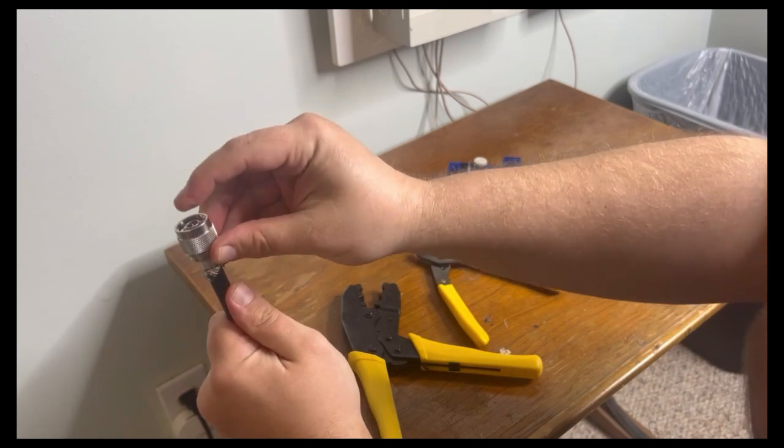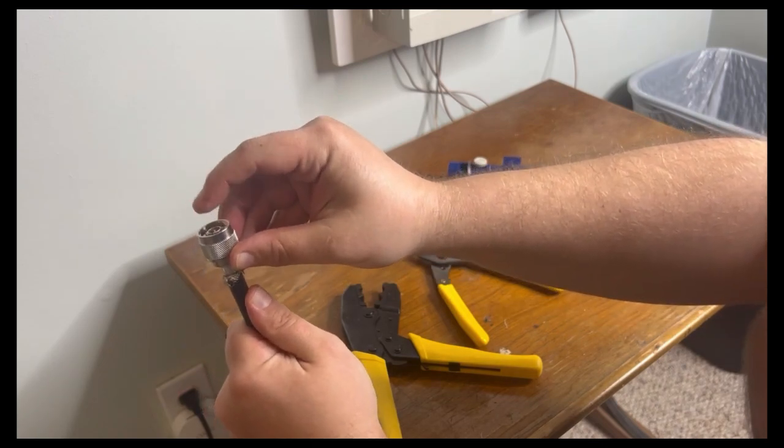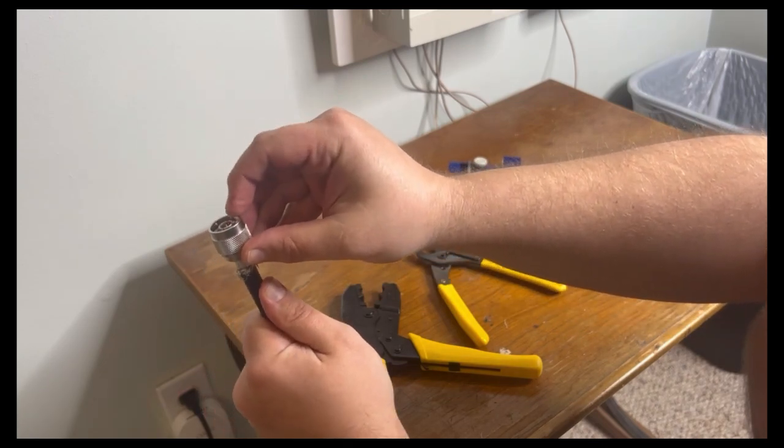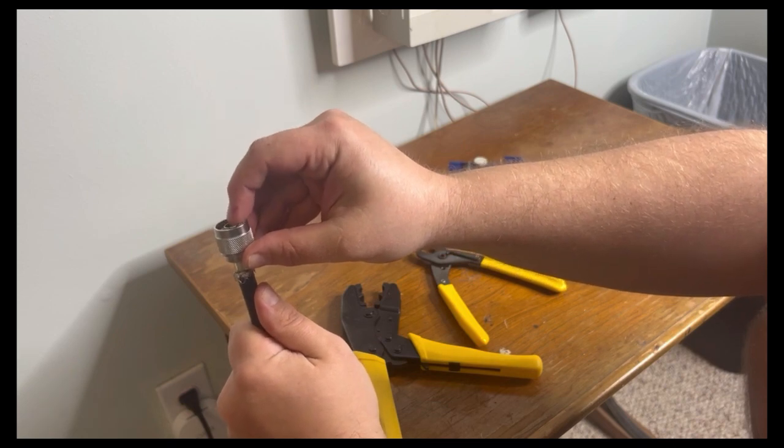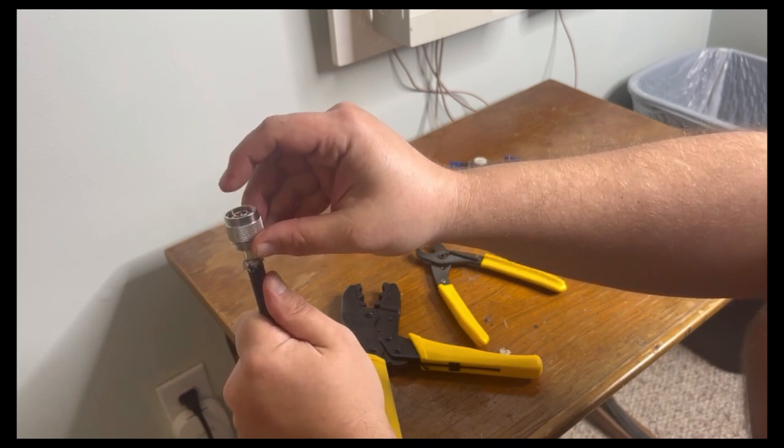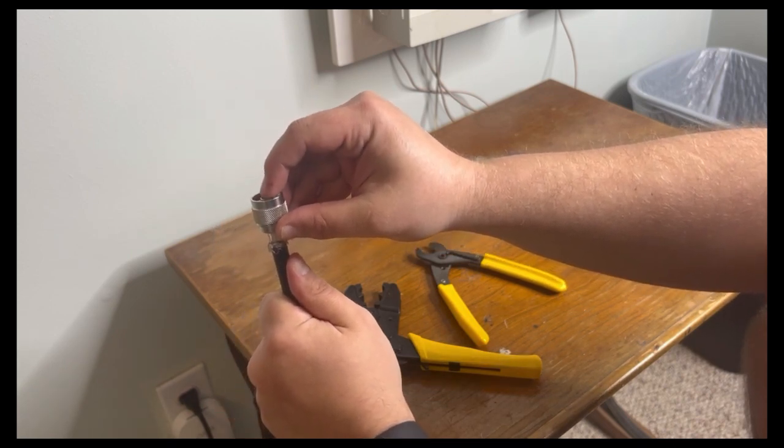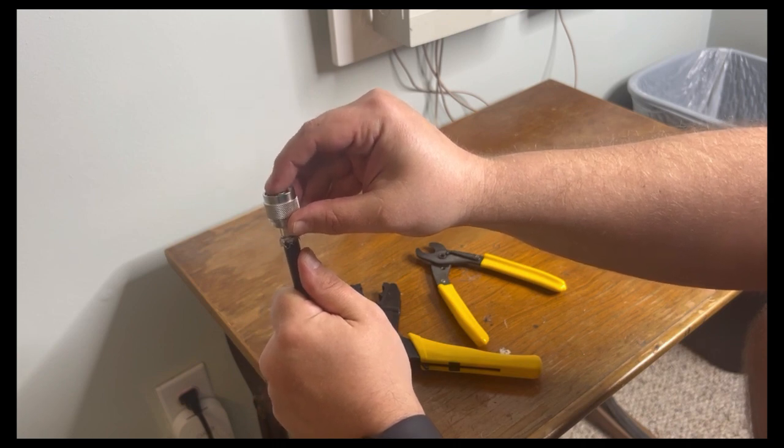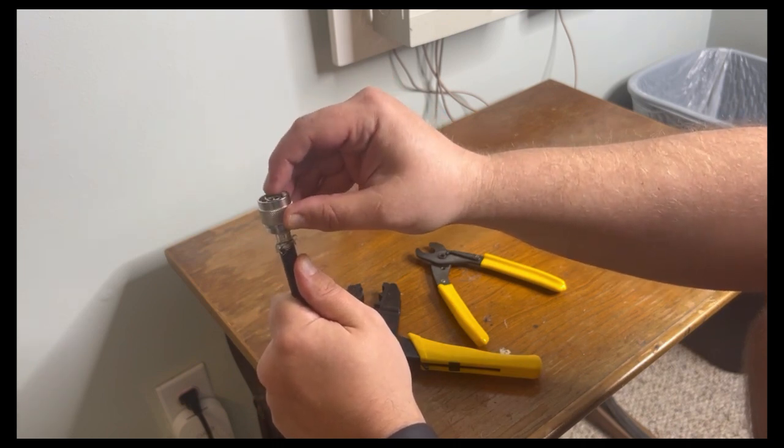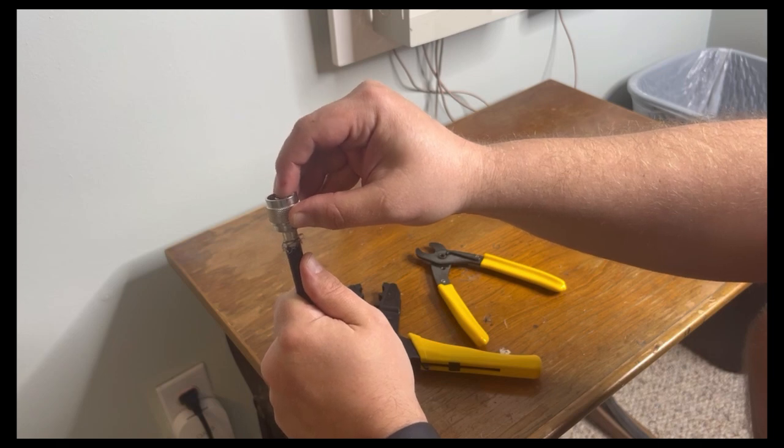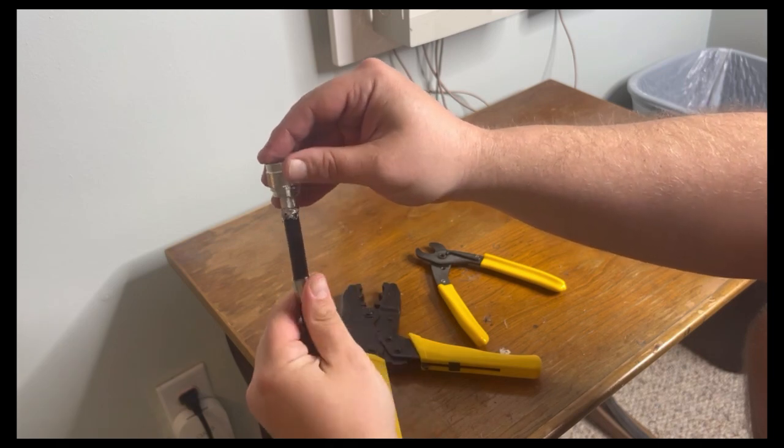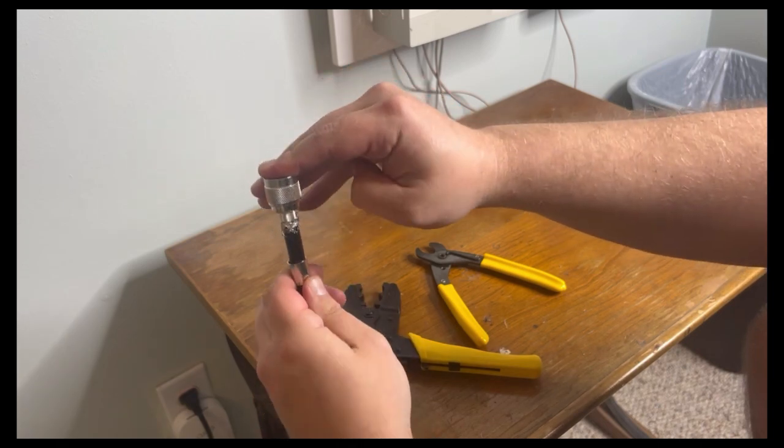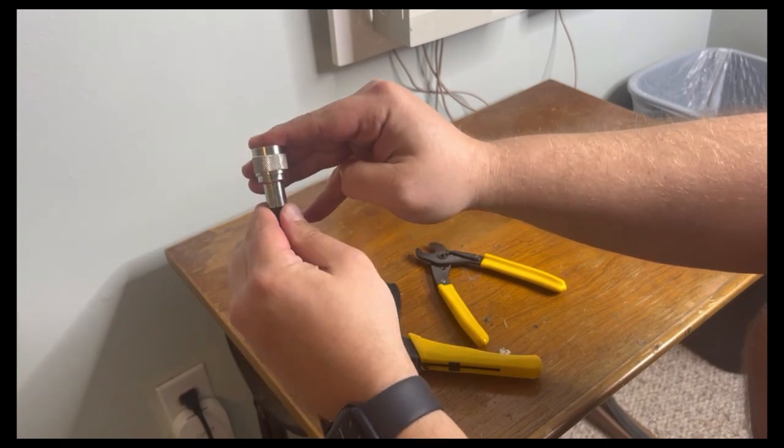Take your finger and feel - the center pin should be recessed an eighth of an inch, just a tiny bit. You should just feel the tip of the center pin with your finger. Now take the sheath and slide it up, pushing all that dielectric back up.